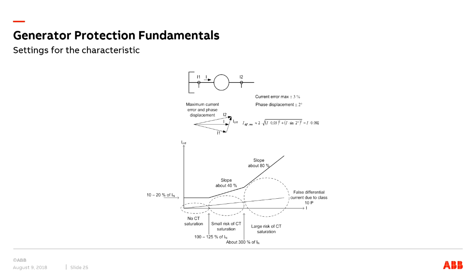In section 2, with large currents, minor CT saturation can be suspected to occur. And in section 3, there is a large risk of CT saturation for external faults. So moving this slope upwards will help combat that situation.